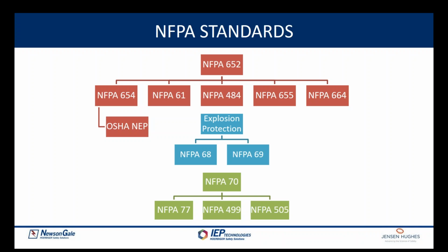The NFPA 652 document is pretty much the umbrella standard, which provides fundamentals of combustible dust and hazards. It also points you to different test methodologies and the occupancy-specific standards, which can be used to identify hazards at facilities and in specific equipment. There are design methodologies such as NFPA 68 and 69. 68 deals with the design of explosion protection by deflagration venting, and NFPA 69 deals with explosion prevention. The National Electrical Code, NFPA 70, also points to 77, which deals with electrostatic hazards. NFPA 499 helps you determine and delineate the extent to which hazardous areas should be established for classified electrical equipment.